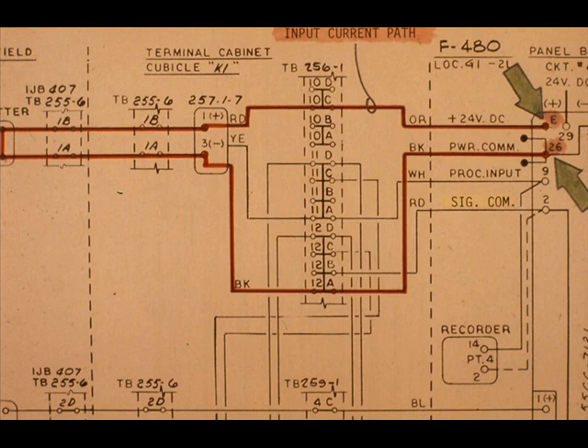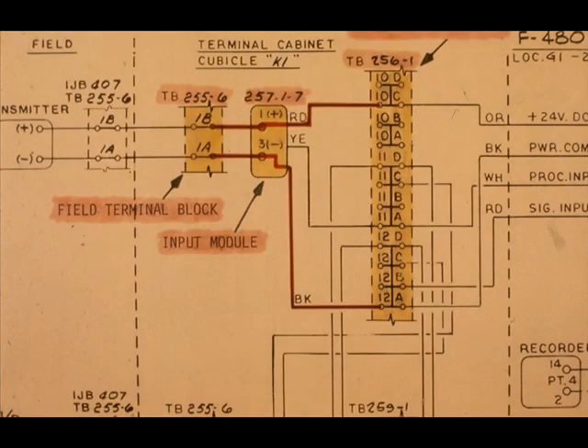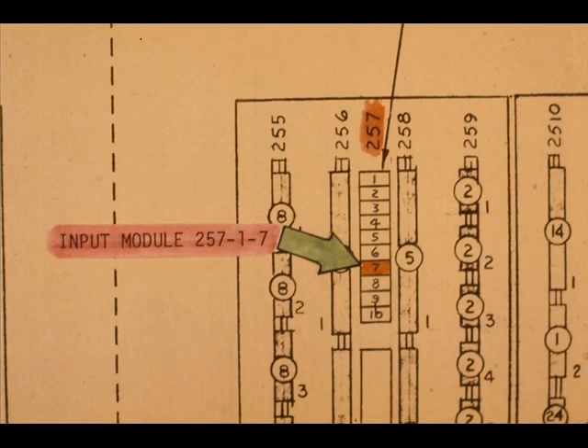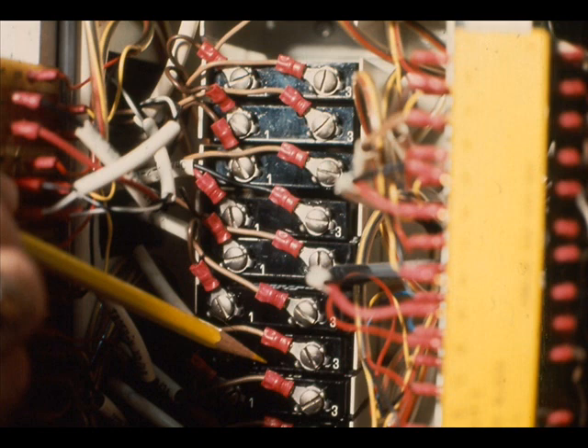The next portion of wiring we will complete is the input current path from the controller to the field terminal block. The input wiring goes from TB255-6, terminals 1B and 1A, to input module 257-1-7. Out of the module to TB256-1, the transmitter block. Input module 257-1-7 is shown here on the terminal directory. It is the 7th from the top in the first group. This is input module 257-1-7. It is the 7th input module from the top.